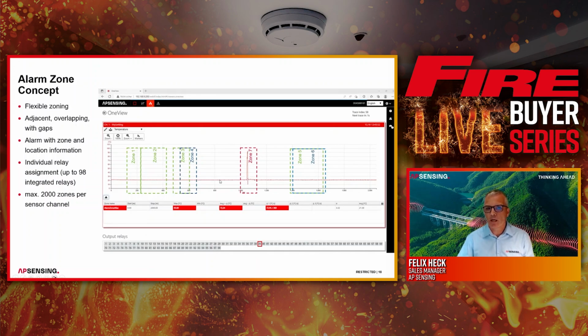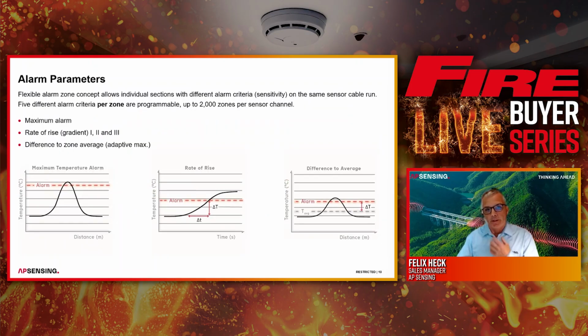There are also parts of the sensor cable without zones. Here it can burn, the sensor cable will see it, the sensor will measure it, but we will not trigger an alarm. This can be, for example, between two buildings, connections between two buildings. For every zone, we can have up to 2,000 zones along the sensor cable per channel. 2,000 zones per channel. And each and every zone can have up to 5 different alarm parameter sets or alarm parameters.